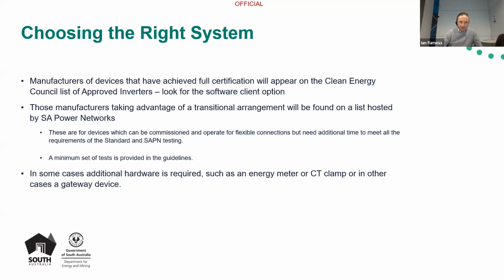Under the most recent revision of our guidelines, we've also allowed for transitional certification. These are devices that haven't ticked all the boxes for full certification against the standard, but have achieved enough to support dynamic exports. You'll find this list on a site hosted by SA Power Networks. Essentially, these manufacturers need to achieve full compliance to allow their devices to be installed from the 1st of April next year, but we're not requiring any changes to devices installed in the meantime.